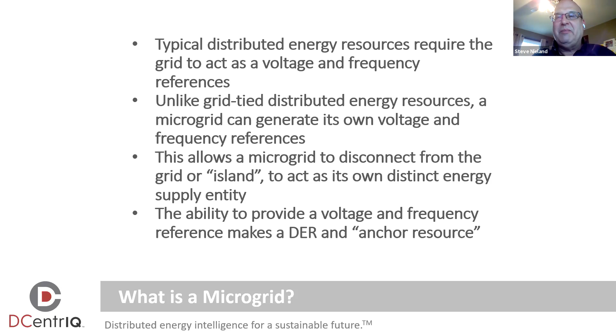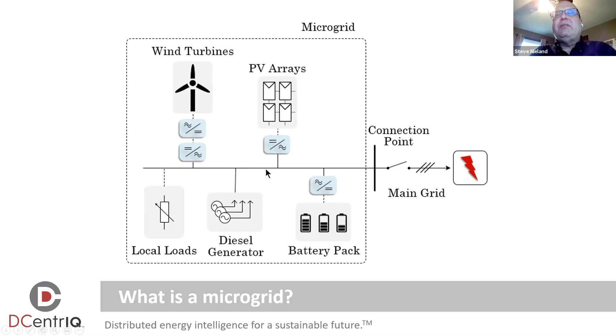So as you look at a microgrid, here's a good example of things that typically can be in one. I've got some form of generation: I've got wind here, a diesel generator here, and some solar. I've got a way to store energy, because the sun doesn't always shine and the wind doesn't always blow. Hopefully one is happening when the other isn't, but I can't rely on that, so I want some way to store that energy. And if I want to be extremely resilient, I want some other generation capability I can rely on in case I don't have enough between all of this. We talked about having loads, because I need a place for the energy to go. I may or may not have a connection point back to the main grid, but the important thing is if I open this connection point, all this keeps working. That's what makes it a microgrid. I'm able to generate a reference and keep on running.